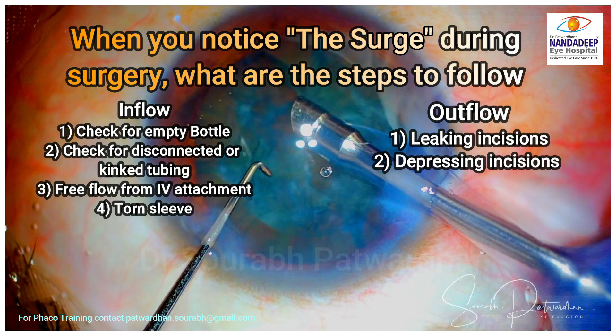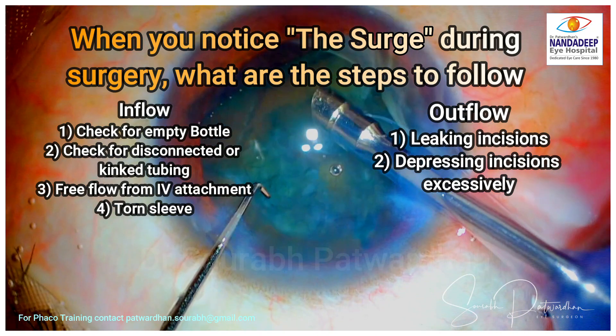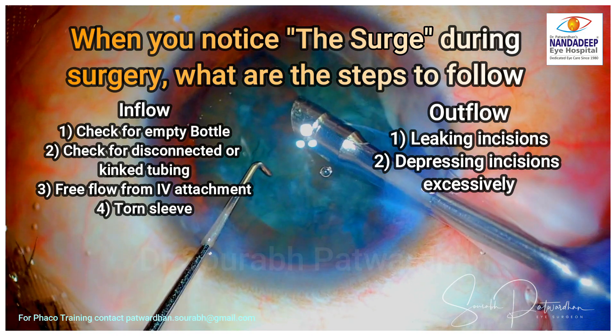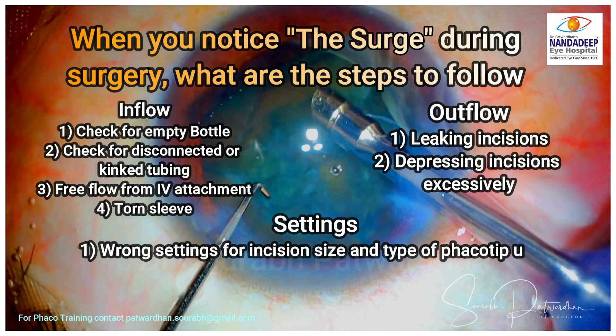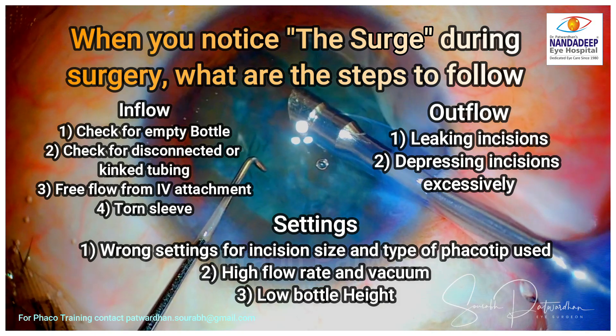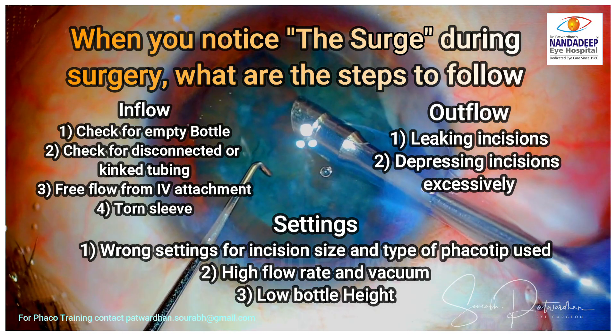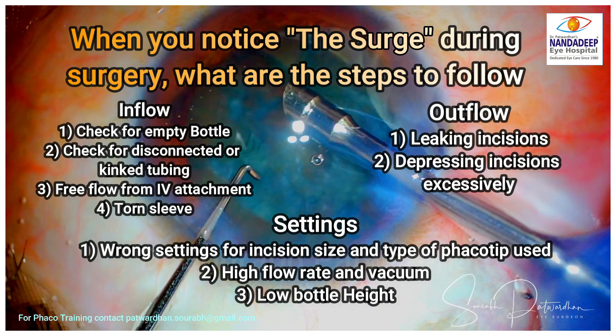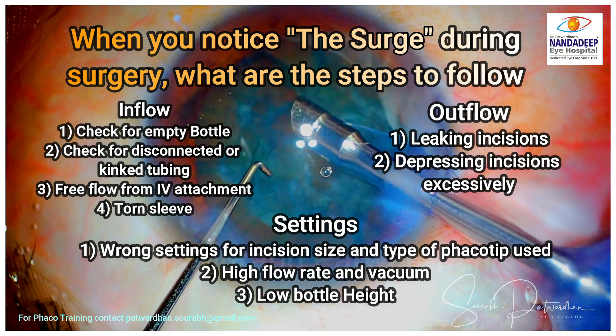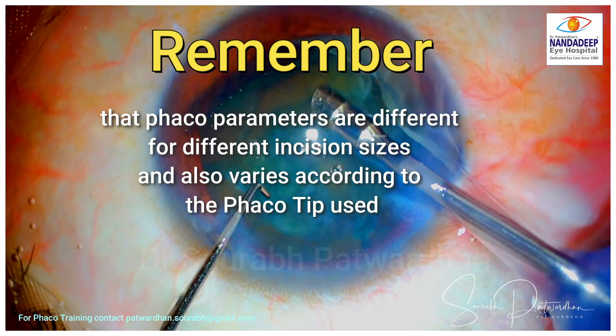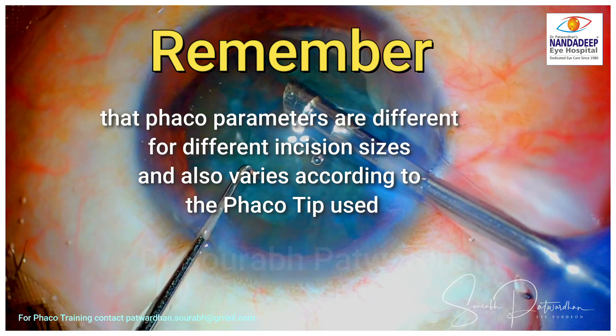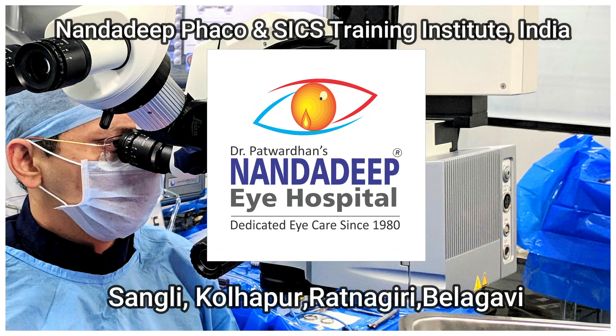If there is a torn sleeve leaking fluid, check the outflow: look for any leaking incisions as in this case, or if you are depressing the incision too excessively during surgery causing higher outflow. Also check the settings — remember that for each incision size and type of phaco tip used, different settings must be used. If you have set very high flow rate and vacuum but placed the bottle too low for those parameters, you may get the surge. Phaco parameters are different for different incision sizes and vary according to the type of phaco tip used, so use appropriate settings.